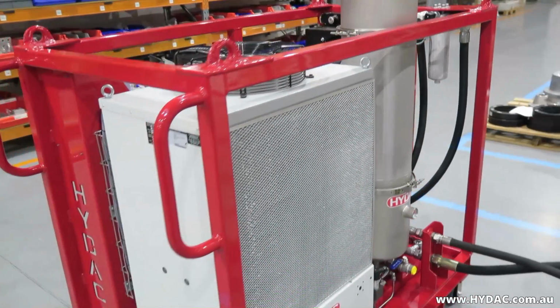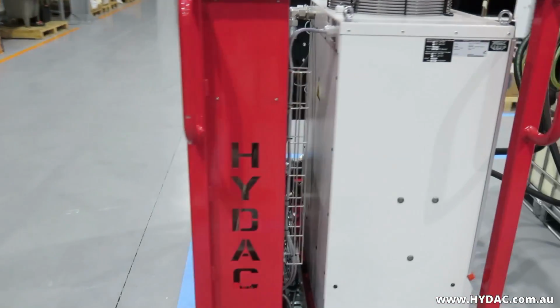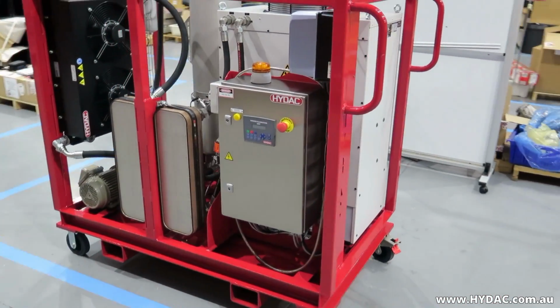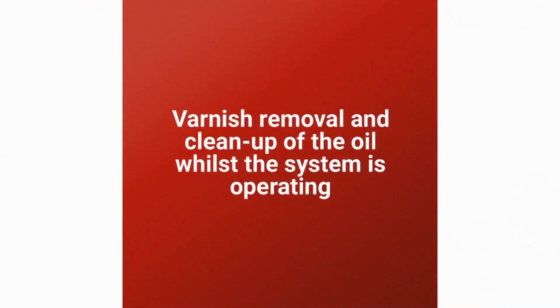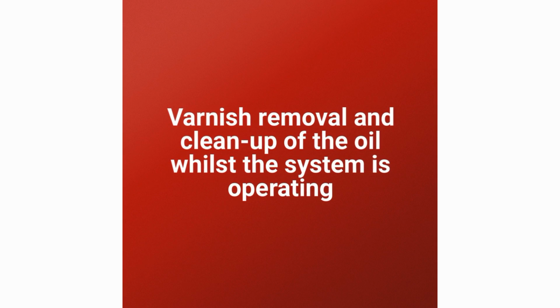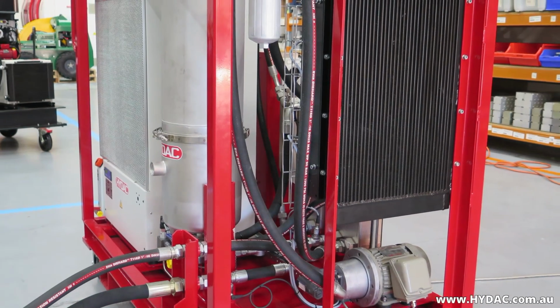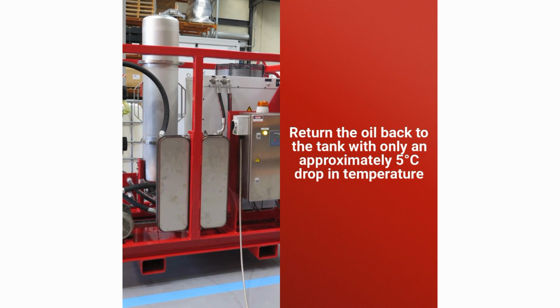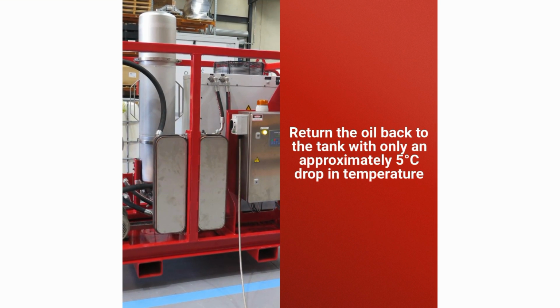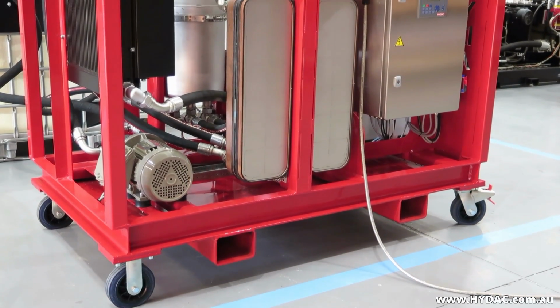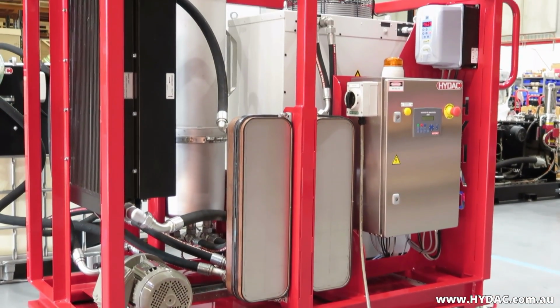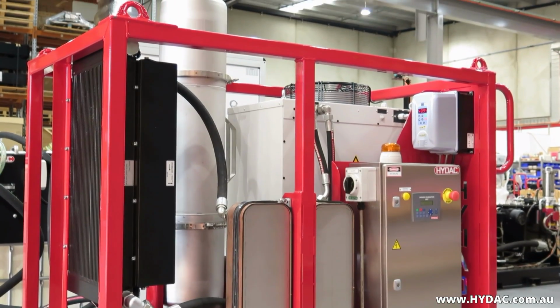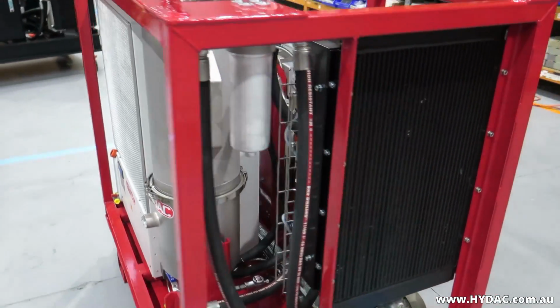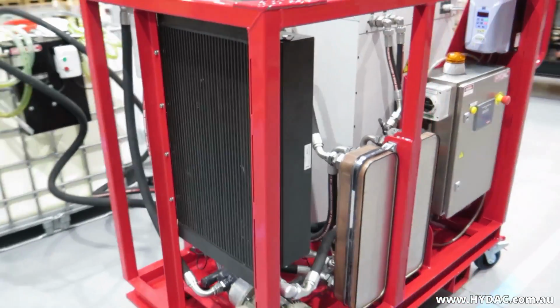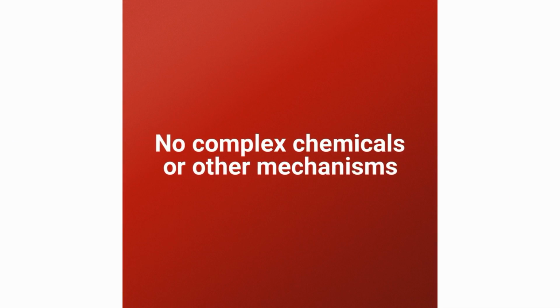The VEU-FAU has the unique characteristic of being a fully online and on-load treatment subsystem, allowing varnish removal and cleanup of the oil whilst the system is operating. The VEU-FAU also returns the processed oil back to the tank with only an approximate 5 degrees Celsius drop in temperature, so that its use will not impact the existing system balance or operation mode, as in there will be no system shock. Additionally, the VEU-FAU uses no complex chemicals or other mechanisms.